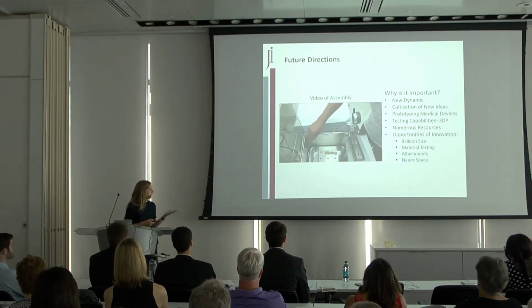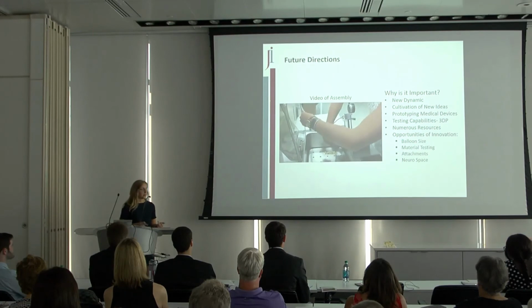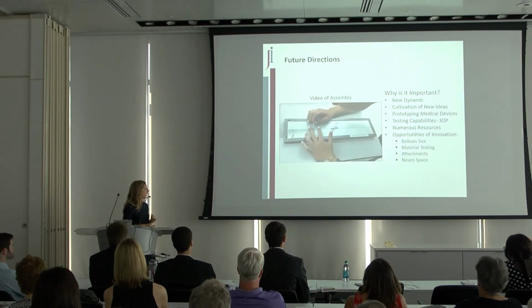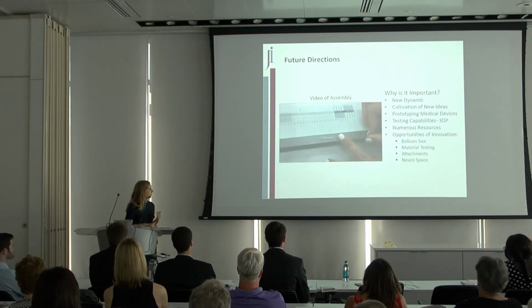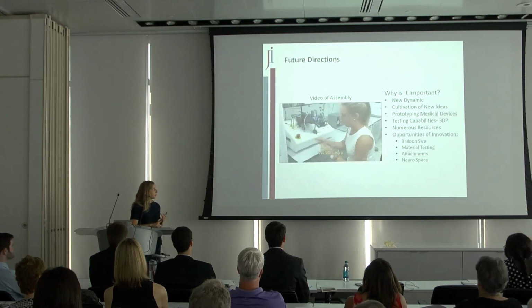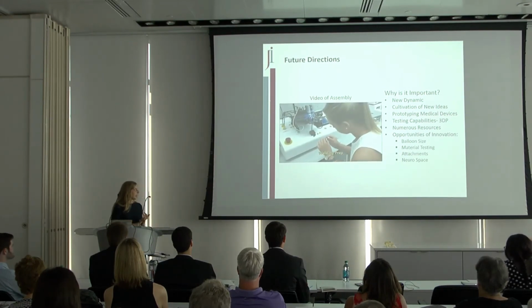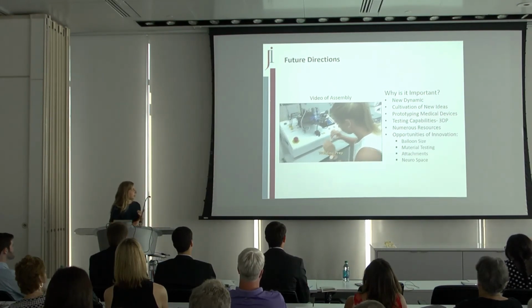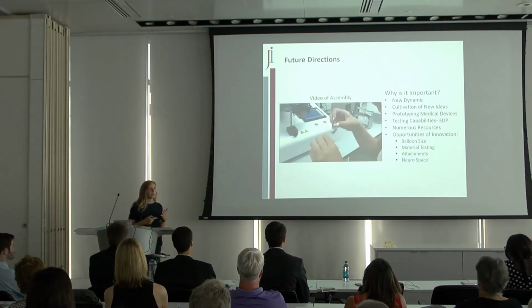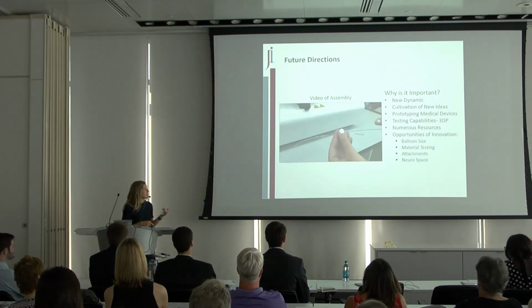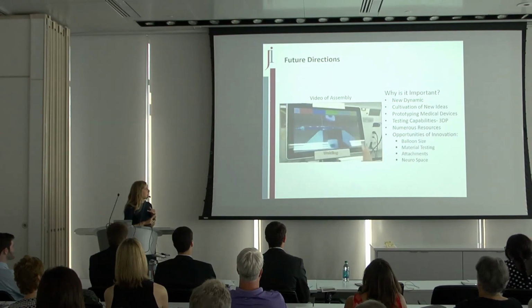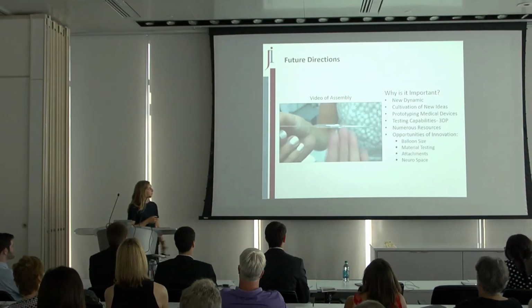And then after balloon forming, we have a balloon, and again, you want to test it to make sure of burst pressure, leaks, and how compliant it is. And then you're going to trim it for welding. Welding prep is, again, a very intricate process. There are 4 materials that you have to include in this assembly before you actually load it into our machinery. So you use a mandrel. The metal will prevent the plastic from welding onto itself, and a welding sleeve protects the outside from welding onto itself. And then you take it out of your machine, and you have your weld.